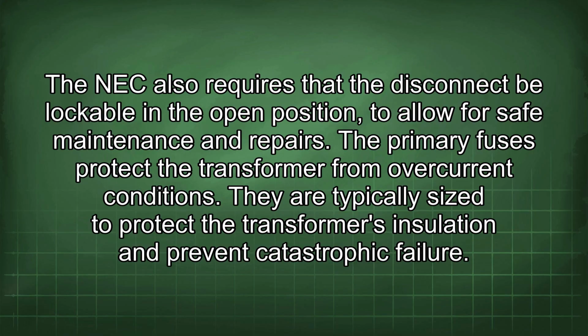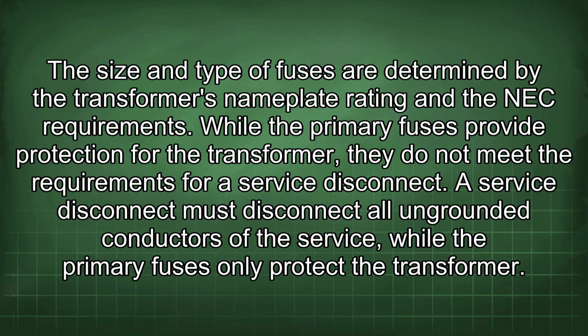The primary fuses protect the transformer from overcurrent conditions. They are typically sized to protect the transformer's insulation and prevent catastrophic failure. The size and type of fuses are determined by the transformer's nameplate rating and the NEC requirements. While the primary fuses provide protection for the transformer, they do not meet the requirements for a service disconnect. A service disconnect must disconnect all ungrounded conductors of the service, while the primary fuses only protect the transformer.